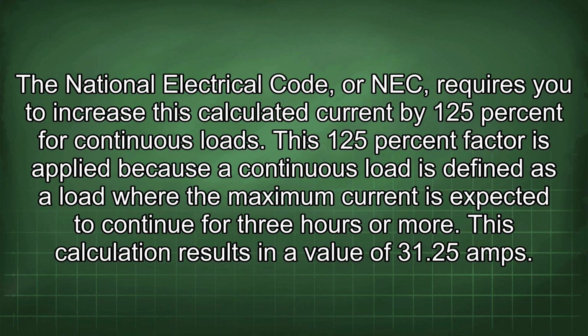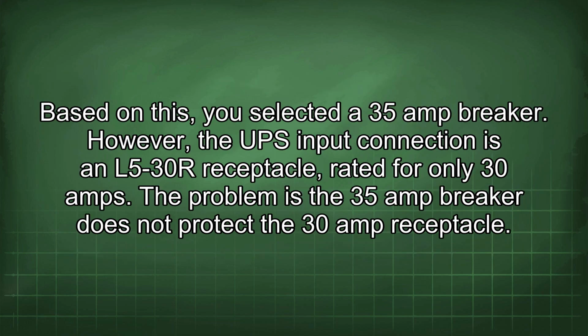The National Electrical Code, or NEC, requires you to increase this calculated current by 125% for continuous loads. This 125% factor is applied because a continuous load is defined as a load where the maximum current is expected to continue for 3 hours or more. This calculation results in a value of 31.25 amps. Based on this, you selected a 35 amp breaker.